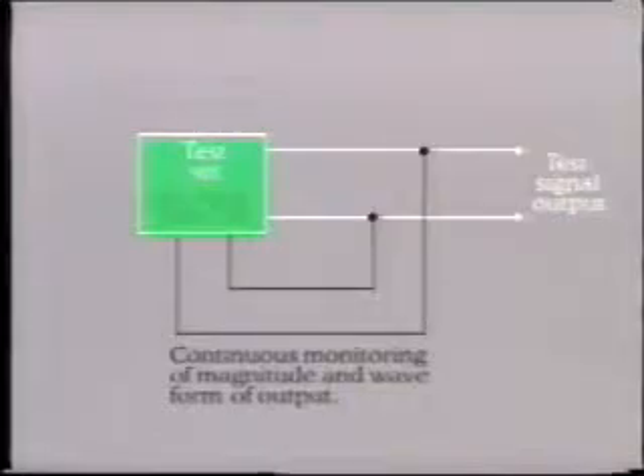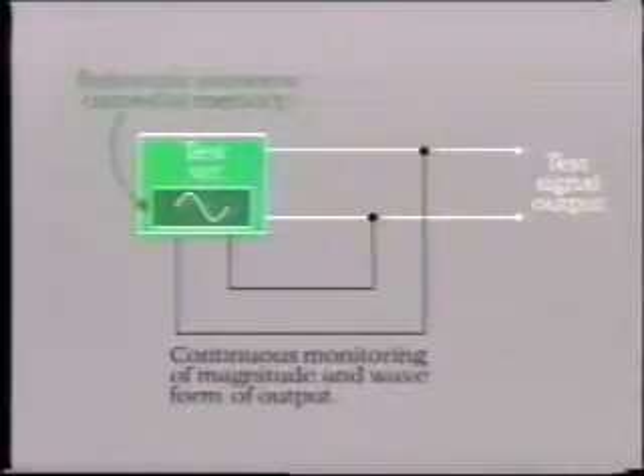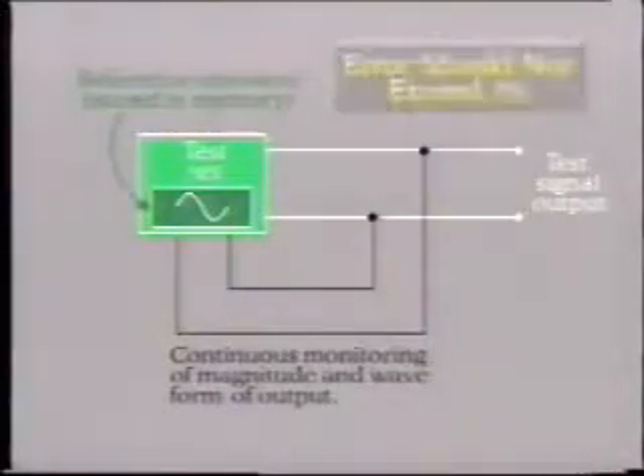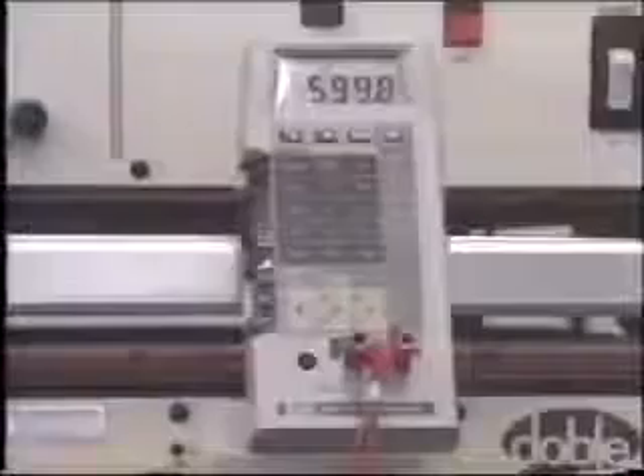The output waveforms are continuously monitored and compared to a precision reference sine wave, which is stored as binary data in memory. The error in both magnitude and total harmonic distortion should not exceed 1%. If a voltage error does occur, we can try paralleling two voltage sources, as long as the phase angles and magnitudes are kept equal. At times, it becomes necessary to supply more current than a single current channel can supply to a relay element, like an instantaneous overcurrent unit. In this situation, it may be possible to parallel two or several current channels.